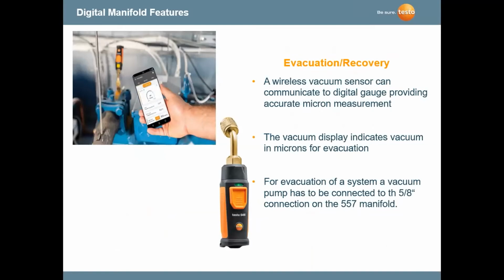This is the wireless probe. We've designed a wireless probe so it's separate from the instrument. This allows for better accuracy because you're closer to the system. You're teed into the vacuum pump, but you're closer to the system, and there's no chance of leaks as you go through if you have a vacuum sensor that's internal in your instrument. Typically, when you pull a vacuum through an instrument, you could create leaks in your connections, your valve stems, even your hoses. This allows us to go directly closer to the system, and it communicates either to the app first or to the digital gauge, whatever method you want to use.